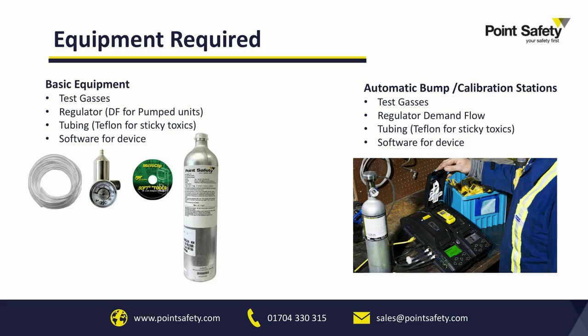If you have a number of meters or you're carrying out a service operation, then you'd probably start considering using automatic bump and calibration test stations. Most meters now will have the option of a bump and calibration station available to them. You would need to purchase a calibration station for each type of device and each type of model. The benefits are it's fully automated. You place the meter into your dock, close the lid, and press a button for bump or calibrate.